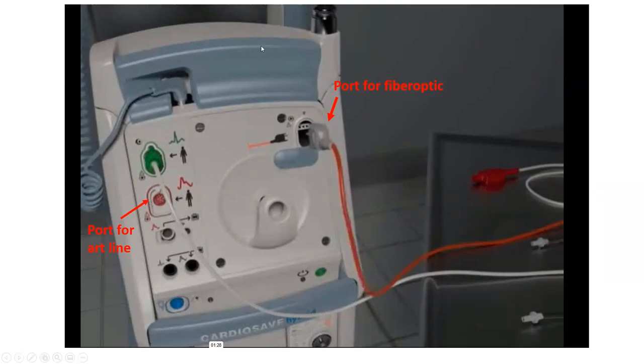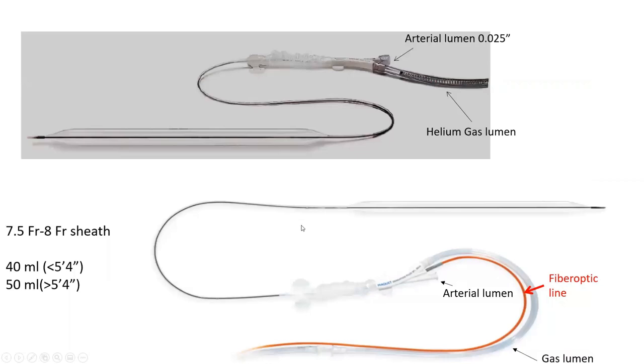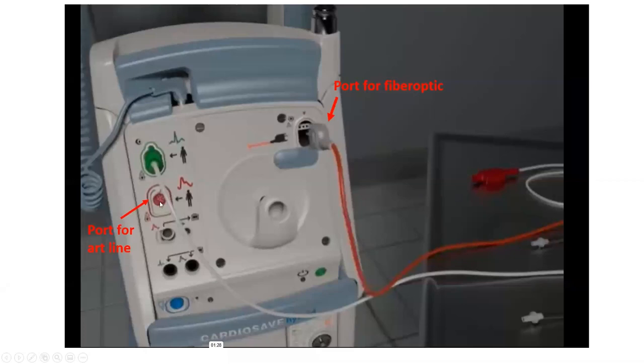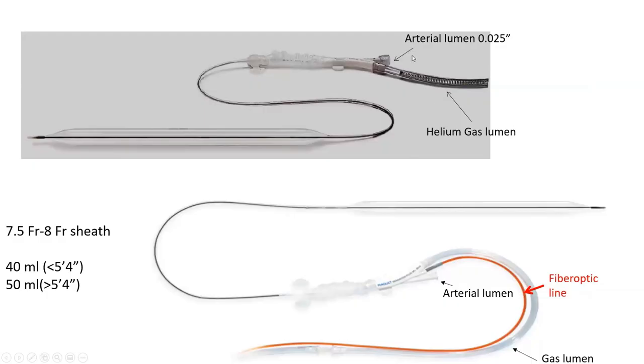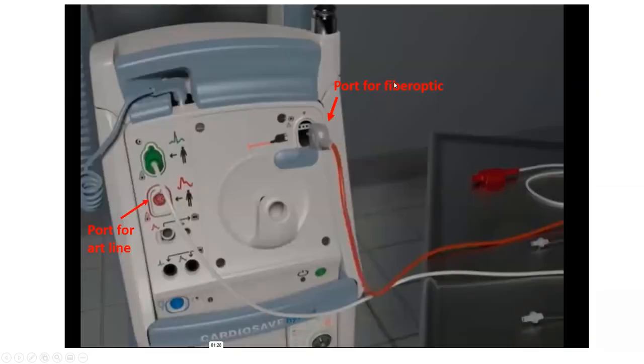Even if you connect it, the balloon pump console will default to using pressure from the fiber optic. If this becomes dysfunctional, then you can connect the arterial line cable if you haven't, and you can use it to monitor the arterial waveform. Also, that cable and that port for the arterial line may be used if you're using a balloon pump that doesn't have fiber optic. And if this lumen becomes clotted, you can use that cable and that port and connect them to a radial line that you connect to a transducer, and you connect its transducer to this cable, then to that port. But that is suboptimal.